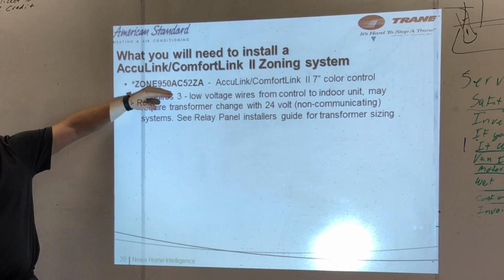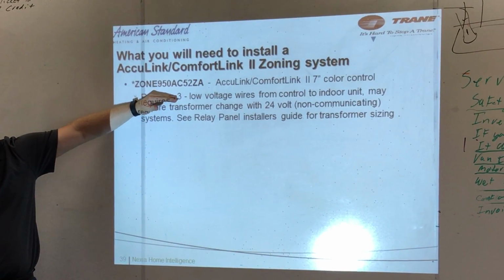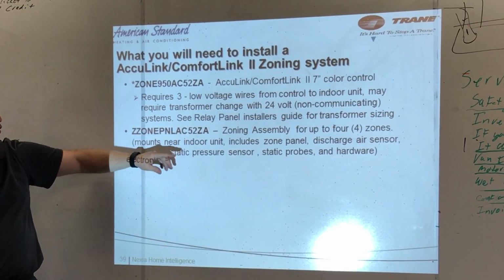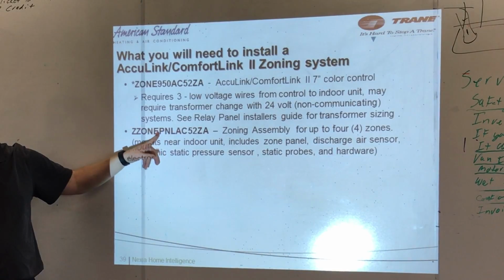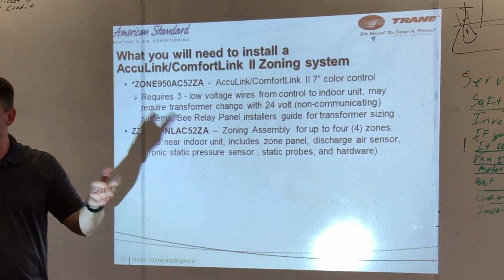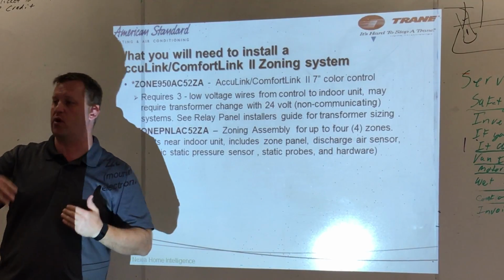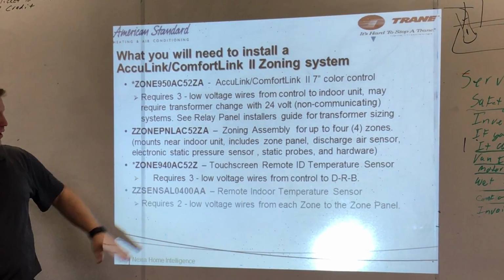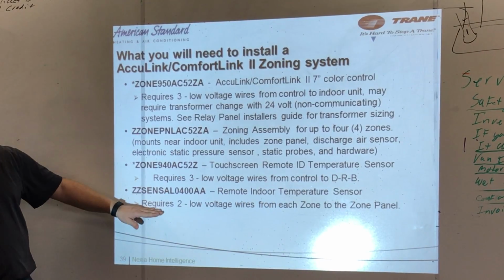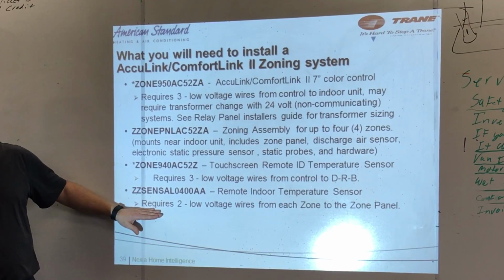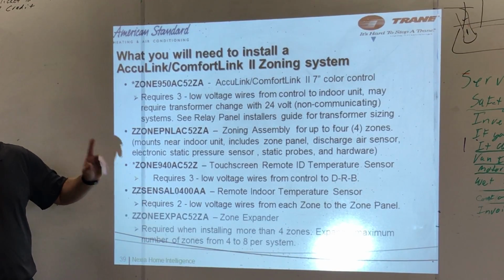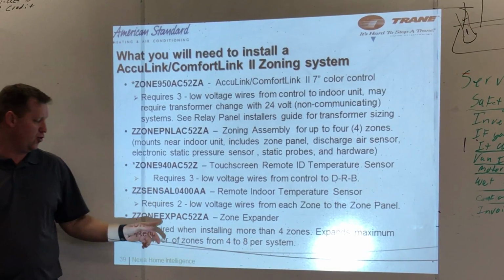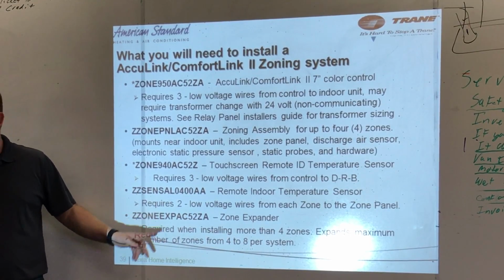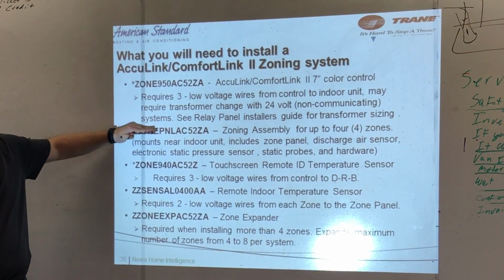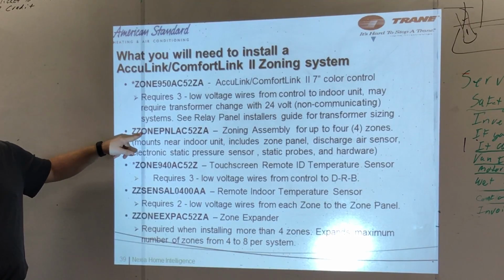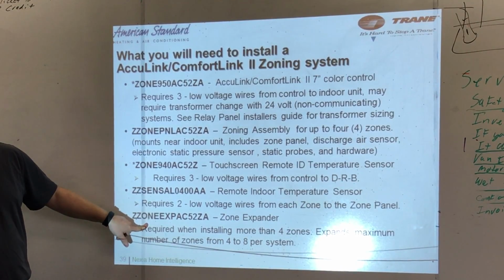Okay, so all right, let's talk about ComfortLink zoning. Have to have a 950. That's the master. Only one master per zone system. Okay. You need the zone panel. You want the zone panel, not the expander panel. Zone panel has a static pressure sensor for the auto zone sizing, has a discharge air sensor, and all the hardware for putting this together. Right. 940 or 0400 sensor for each of the zones, 2 through 8. Okay. We can only go up to 8 zones. If you go beyond 4 zones, you have to get the zone expander panel. Which, guys, literally the only difference between this and this is this has all of the accessories in it. This is literally a panel only. Okay?